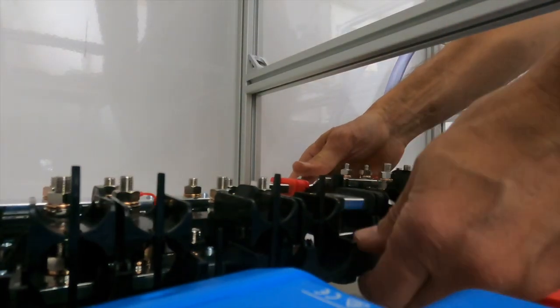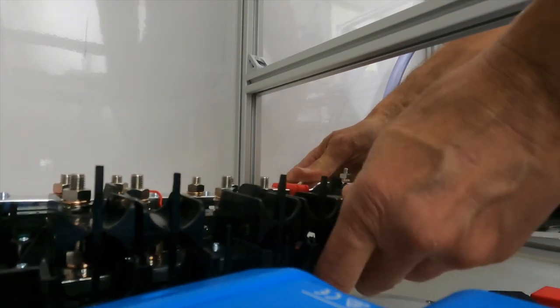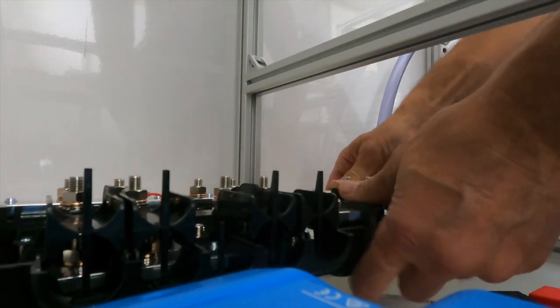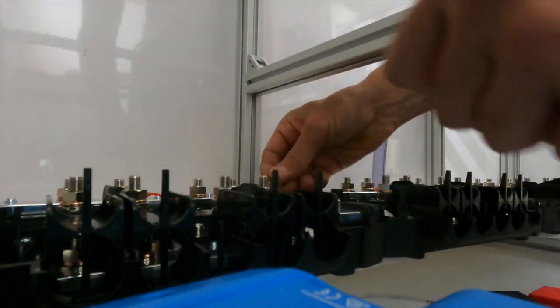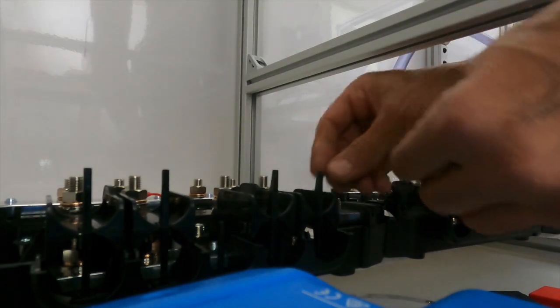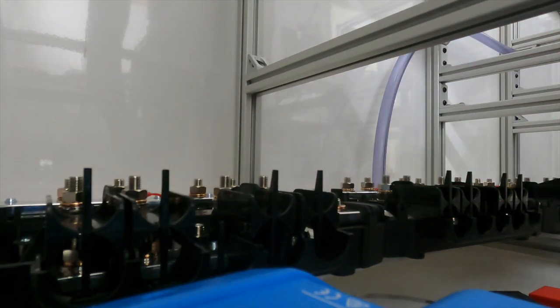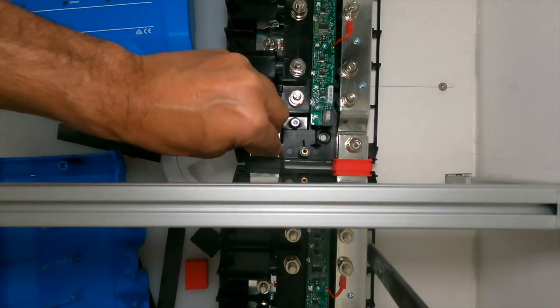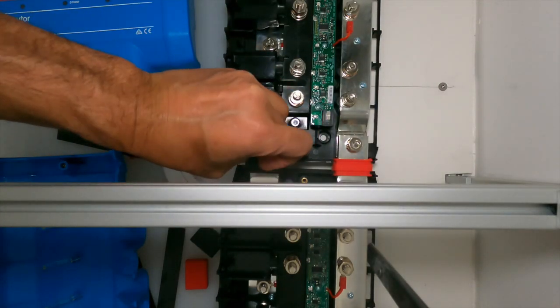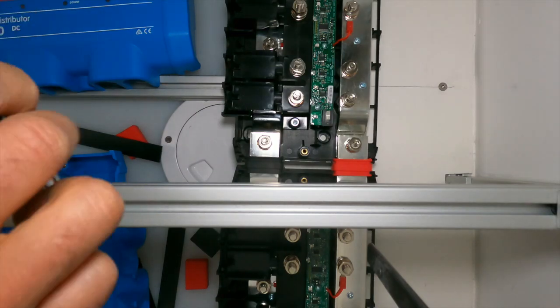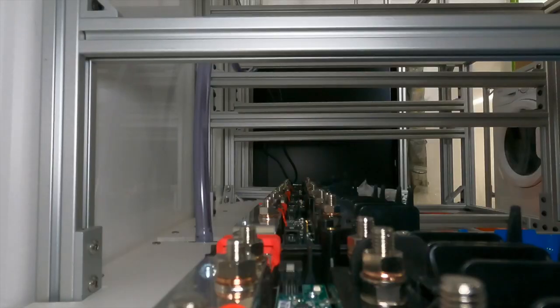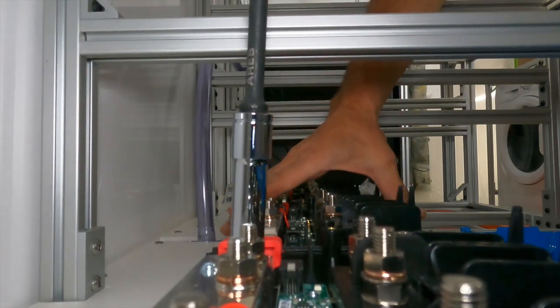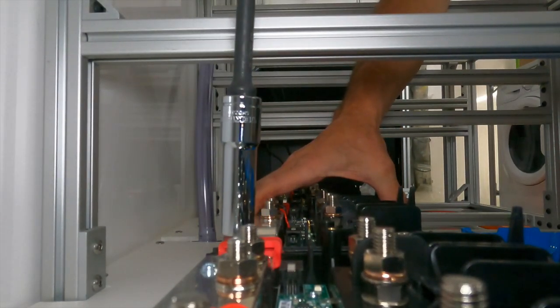Now I have to do the same tetris with my Lynx Distributors and shunts. I need to minimize the length of the battery cables, both positive and negative, from each battery pair and ensure they're all equal length with each other so they have equal charging and discharging.